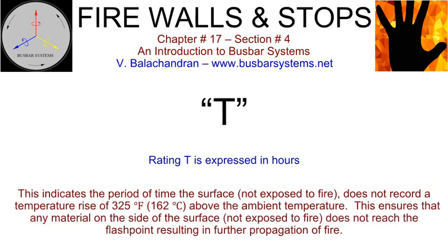Rating T is expressed in hours. This indicates the period of time the surface which is not exposed to fire does not record a temperature rise of 325 degrees Fahrenheit or 162 degrees Celsius above the ambient temperature. This ensures that any material on the side of the surface that is not exposed to fire does not reach the flash point, resulting in further propagation of fire.